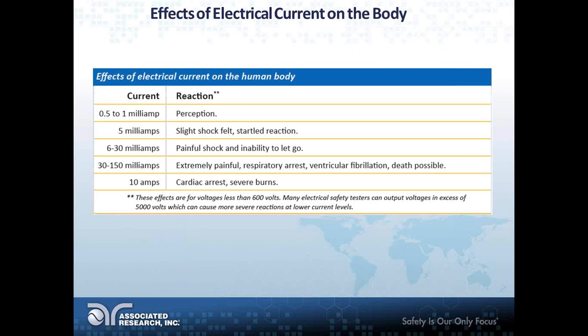You might definitely feel something below the perception level I've listed if you're dealing with 5,000 volts as opposed to 500 volts. The 600 volt mark, around 6 to 800 volts, is actually the breakdown voltage of human skin. Human skin does provide insulation — it's a barrier, it is an insulator — but it has a breakdown voltage like any other insulation, and when that happens, that's when there's trouble.